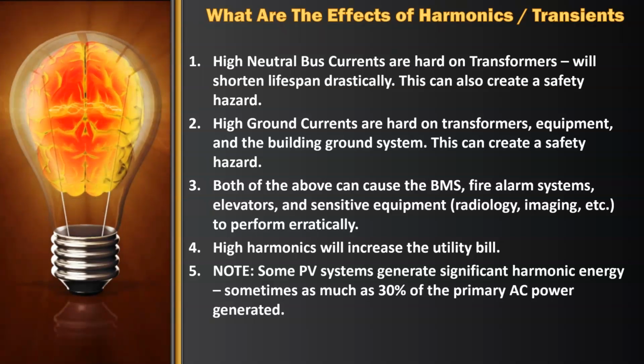So what happens when you do that is that you turn on the array, and the array puts out 1 meg, and you're looking at it and it looks like it's okay. Maybe it's somewhere between 900 kilowatts and a meg. But for some reason, when you turn it on, the building energy use goes up by about 200 or 300 kilowatts. And you can't really understand why that's happening. So, well, it's because the harmonic from the array is going back into the main service, and the meter is counting it. So we do want to be aware of that, and you can see that when you turn the array on and off, you can watch the power use go up and down.